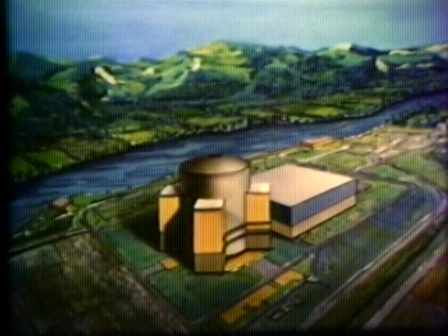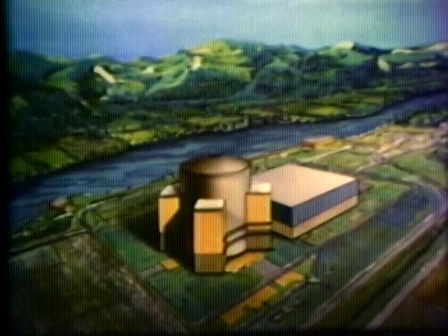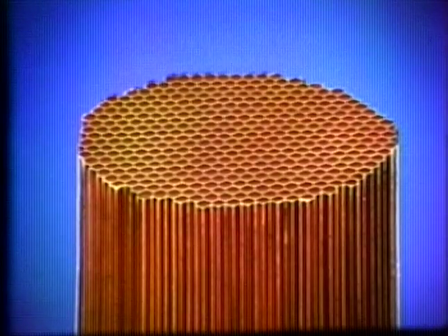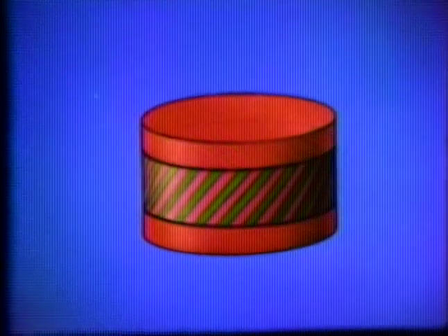This completes the description of the 4 main systems in this nuclear power plant, noteworthy primarily for the presence inside the reactor building, at the center of the main vessel, of fuel assemblies containing fissile and fertile material for the breeder reaction. The mixture of plutonium and depleted uranium comprising the Superphénix core occupies a cylindrical volume 1 meter high and 3.6 meters in diameter. This core is surrounded by a fertile blanket approximately 30 centimeters thick.